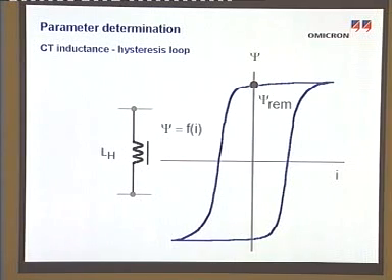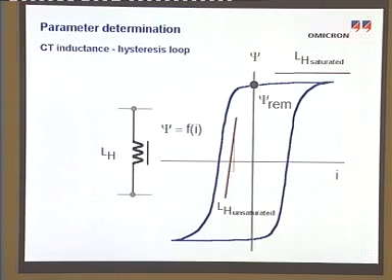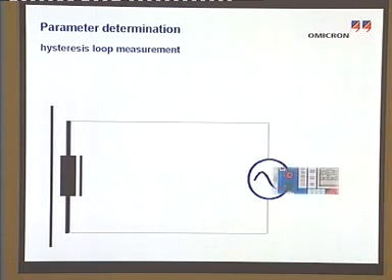Remanence, non-saturated and saturated magnetizing inductance are characteristic parameters which are often only available with difficulty. Because of this, the following procedure for direct measurement via relay test equipment was developed. A sinusoidal voltage is connected to the secondary transformer terminal. The primary test system, CPC100, is designed particularly for CT and VT testing.